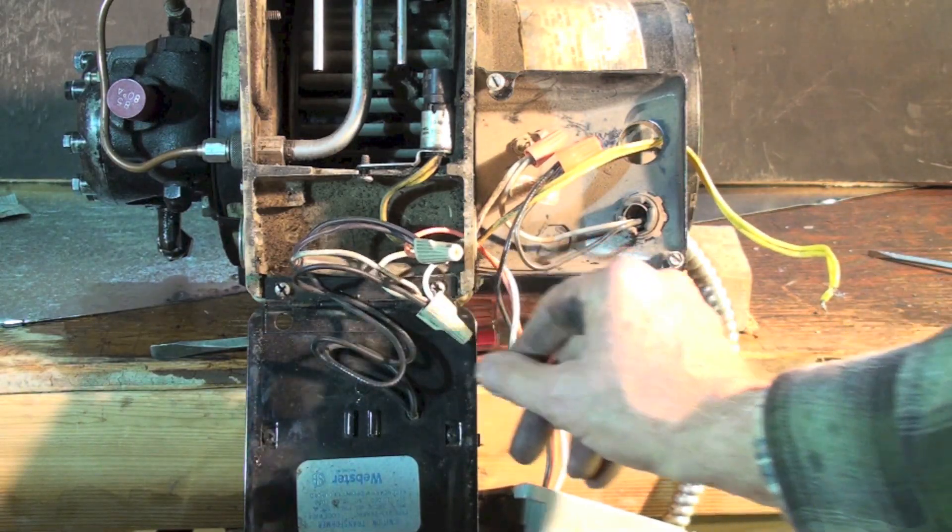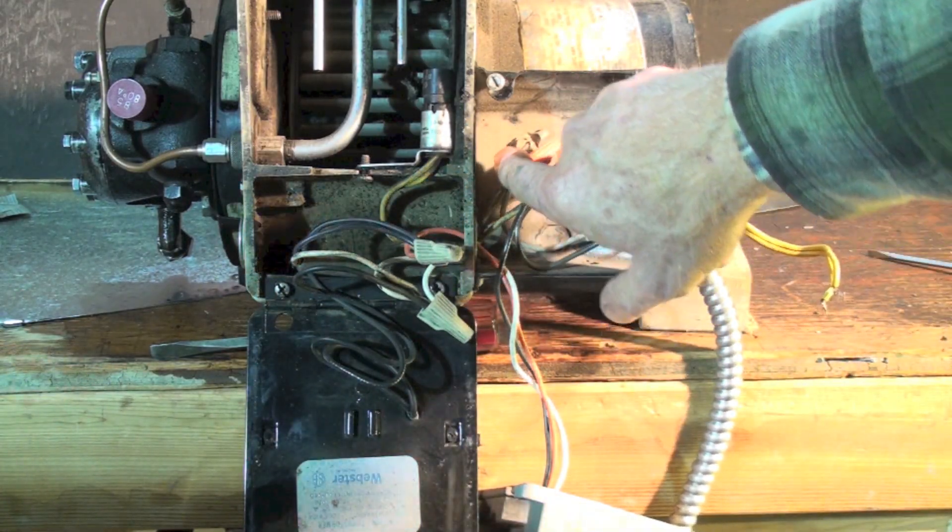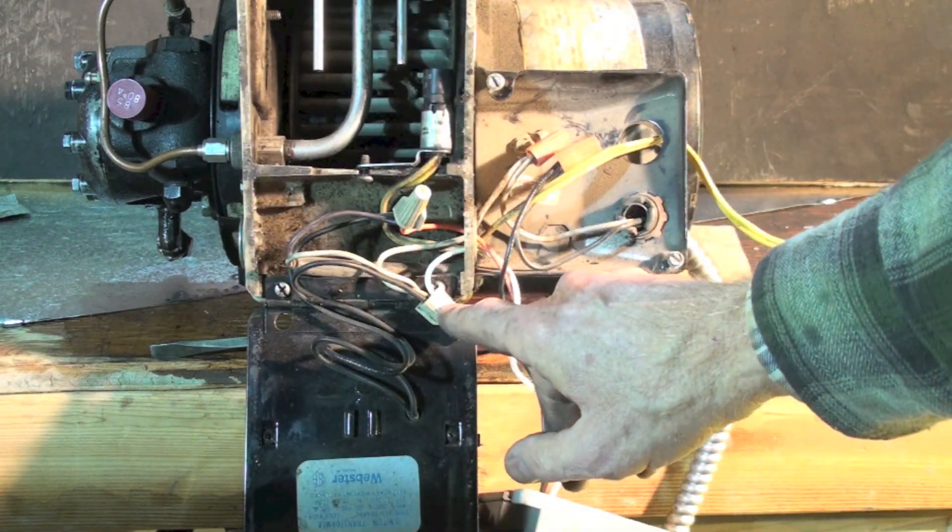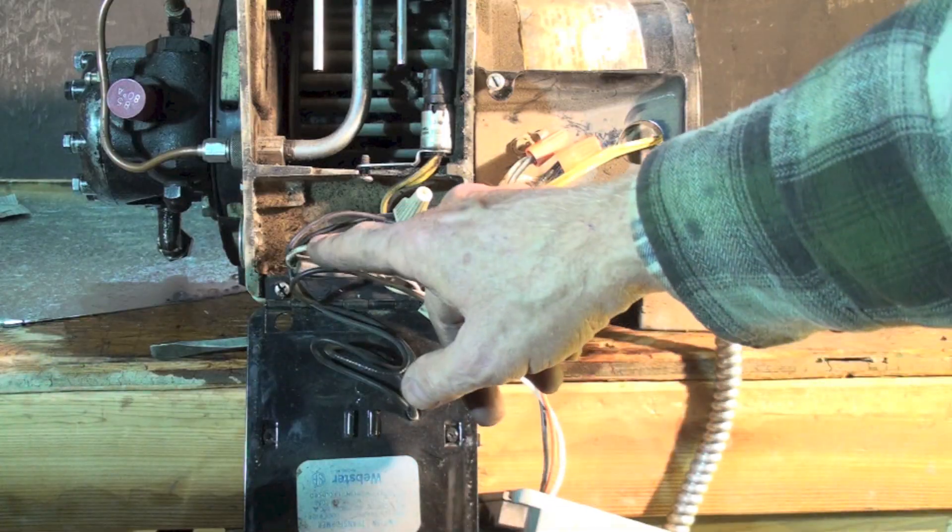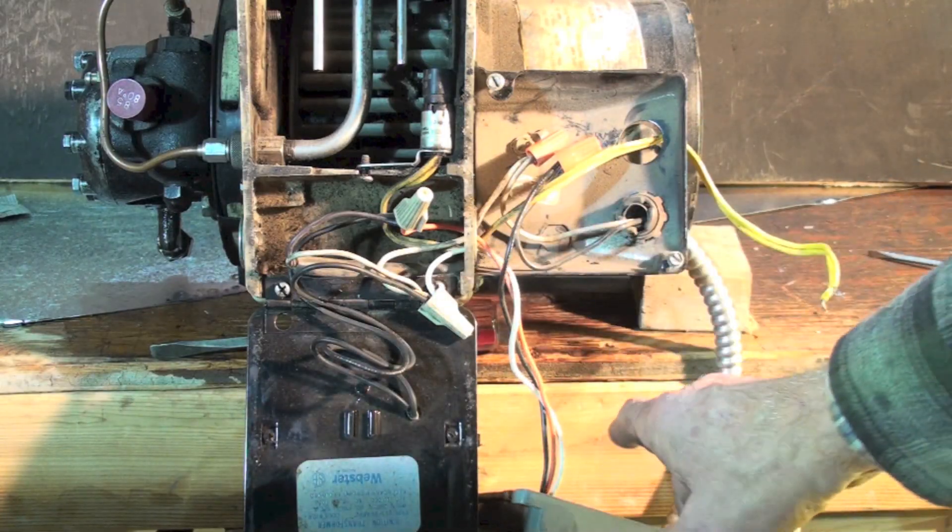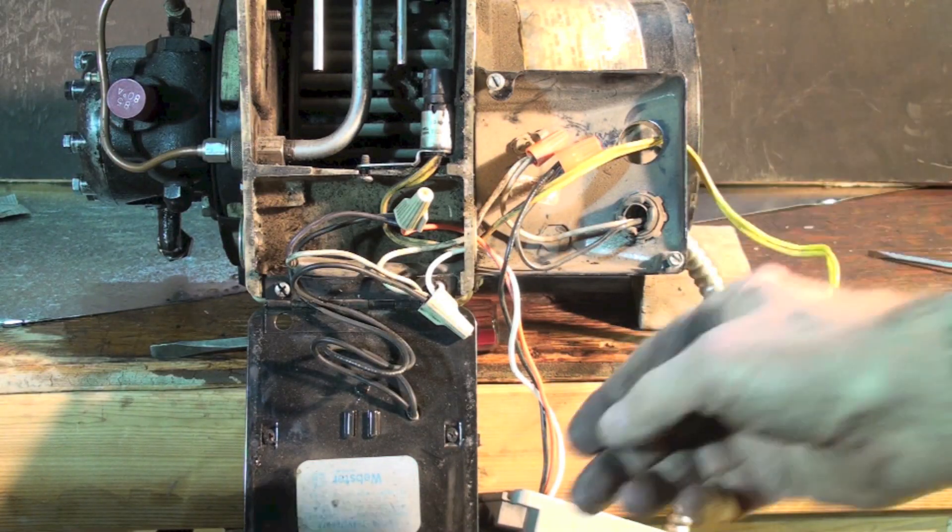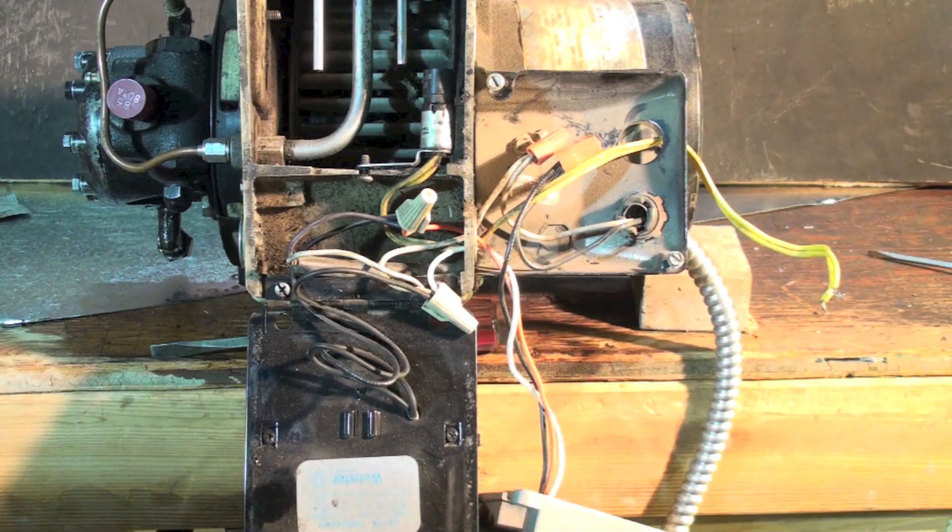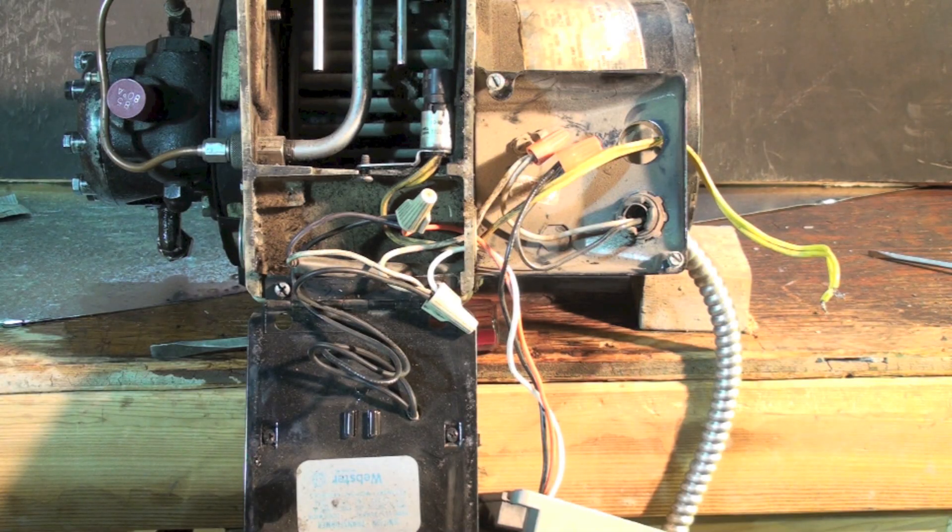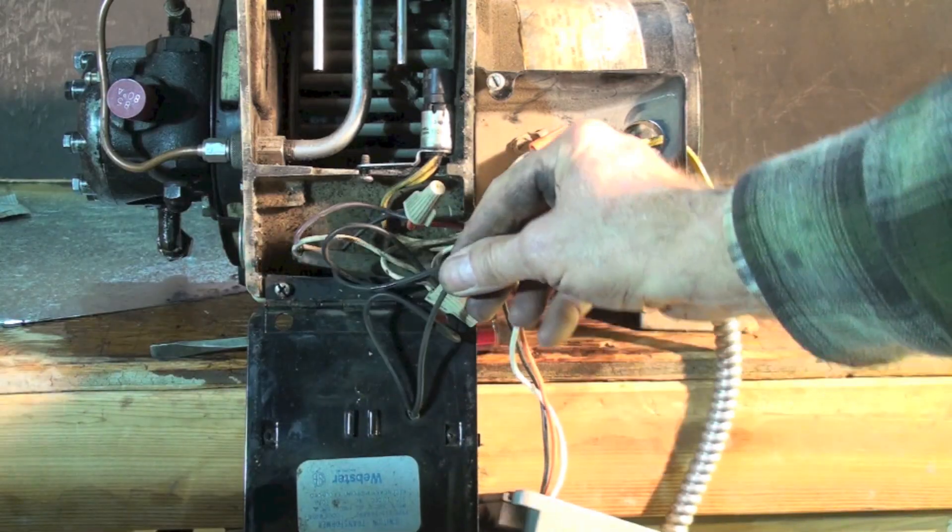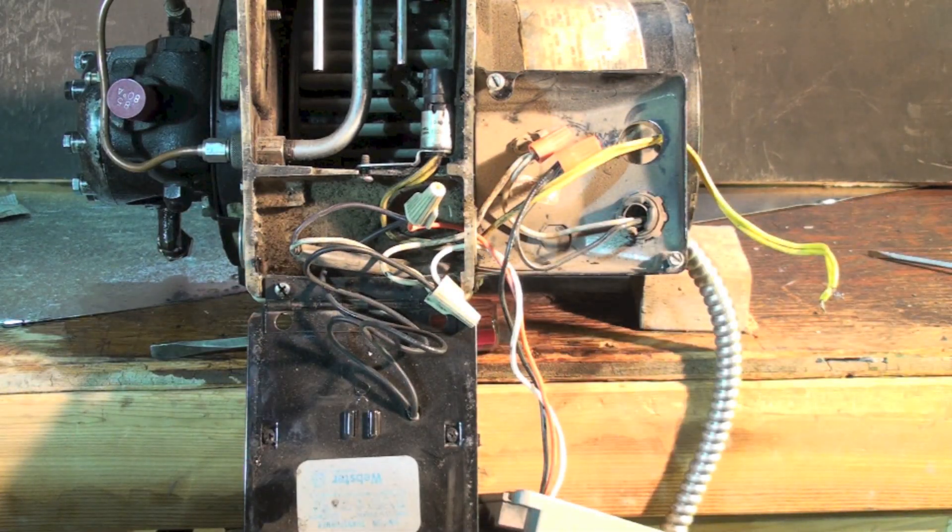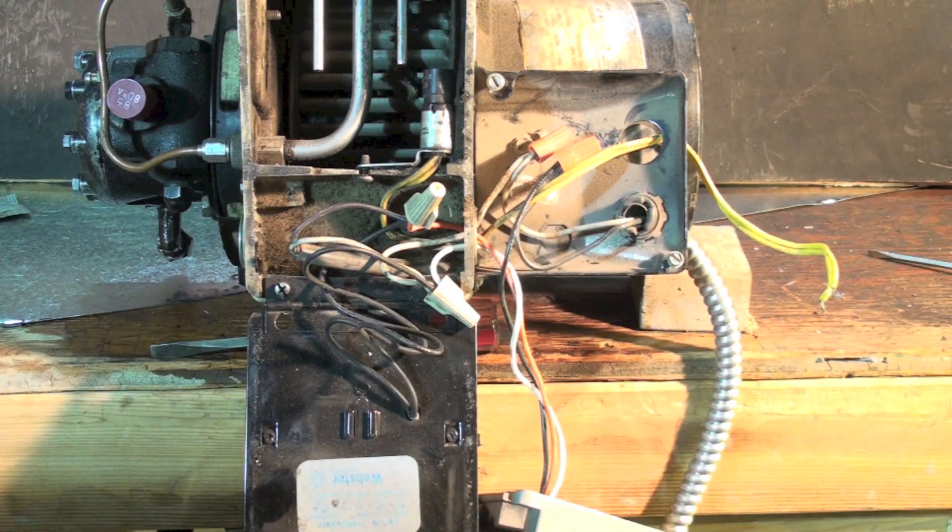So we have the white wire coming from the power source goes to a wire nut in here. One goes to the motor, one goes to the cad cell relay. The only odd man out here is the transformer, because both wires going to the transformer are black. Doesn't make any difference which one you use. Just hook up one of the black wires from the transformer to that white wire nut.